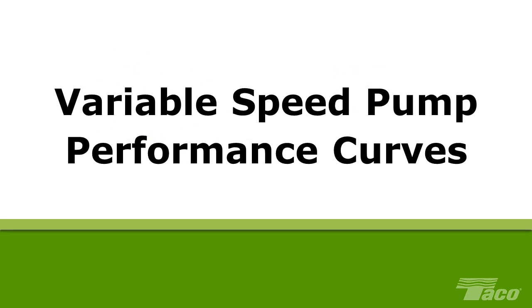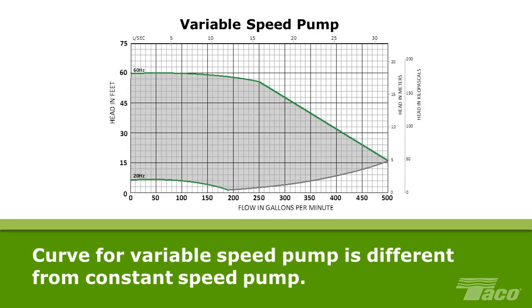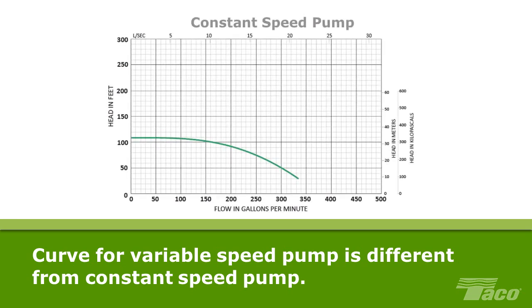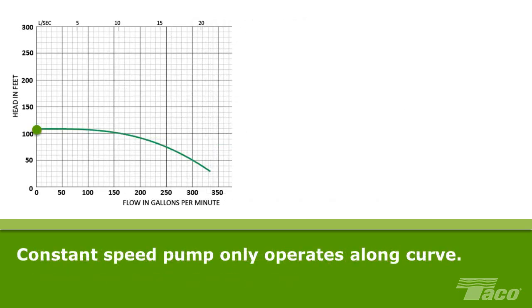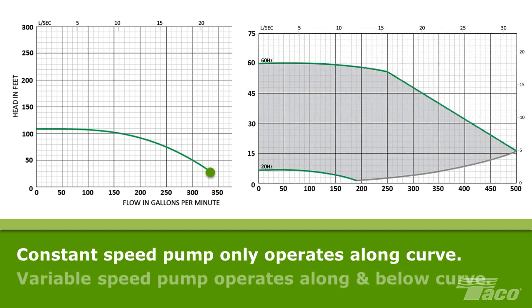Variable speed pump performance curves. The performance curve for a variable speed pump is significantly different from that of a constant speed pump because of a fundamental difference between the two types of pump. Where a constant speed pump can only operate along its performance curve, a variable speed pump can operate anywhere along the curve or below it.